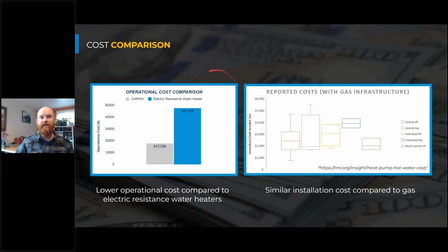So on the left-hand side of the screen, we have our operational cost comparison, and we have our commercial heat pump water heating system in gray and our more typical electric resistance water heating system in blue. So we can dramatically reduce the operational costs here. It is coming in at about 40% of that electric resistance baseline assumption. For gas, right now, gas is about, or has historically been about 1/3 the cost of electricity.